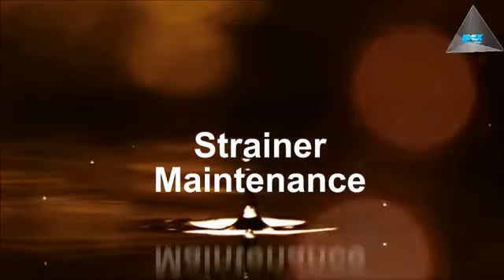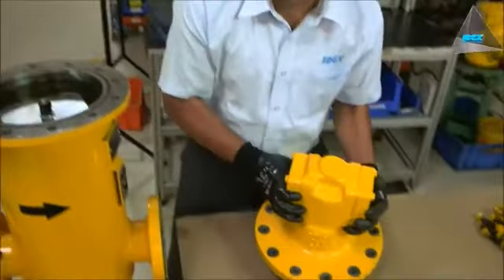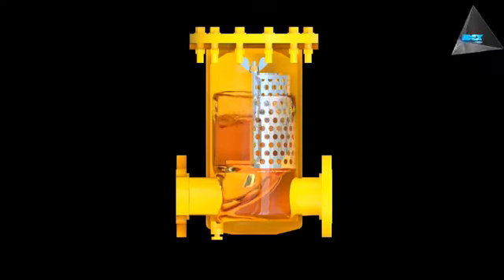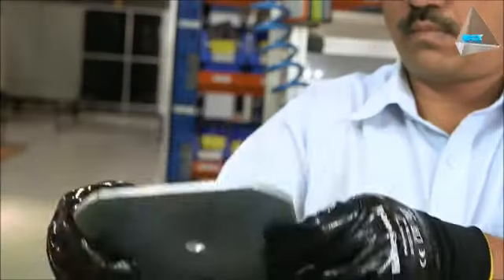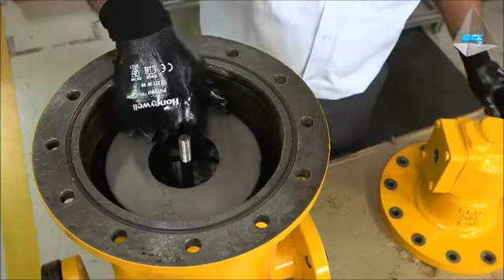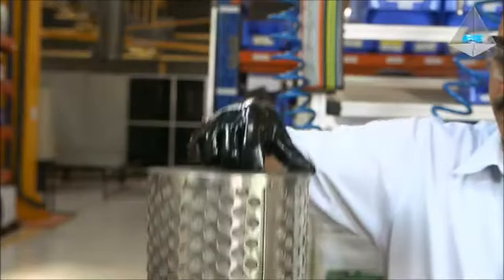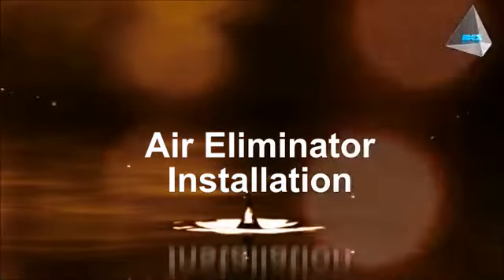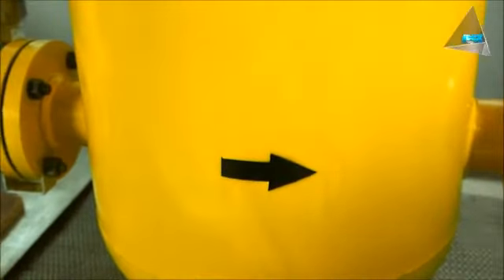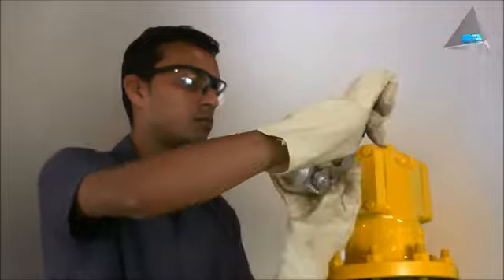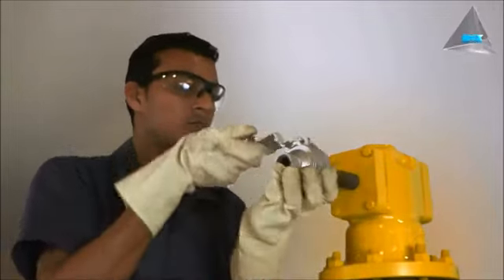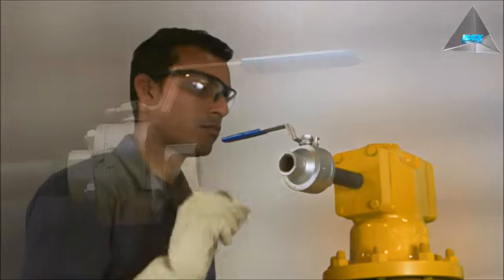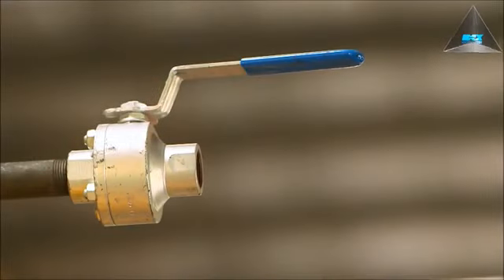Strainer maintenance. Check the strainer daily during the first 100 hours of operation or until no more debris is found in the strainer. Thereafter, the strainer should be checked once every 3 months. The frequency may vary based on any specific service conditions, throughput and product cleanliness. Air eliminator installation. Look for the arrow marking for proper flow direction. The vent of the air eliminator should be at atmospheric pressure. The vent is provided with a ball valve. The ball valve is to be kept in the open condition all the time, except in the event of any leakage.